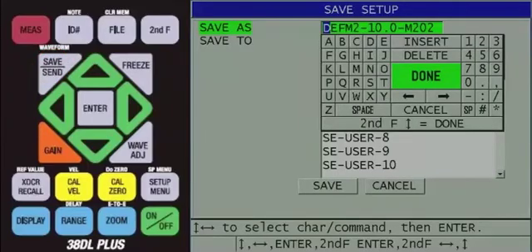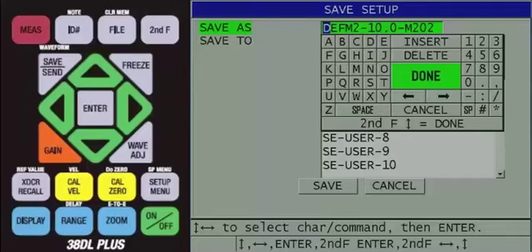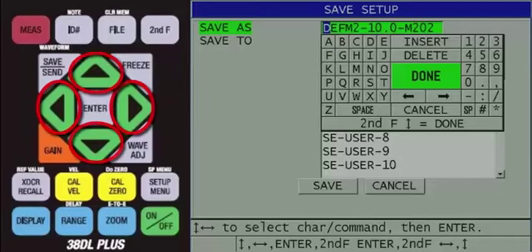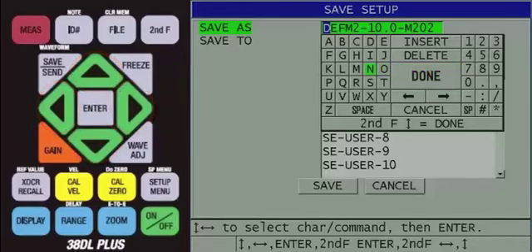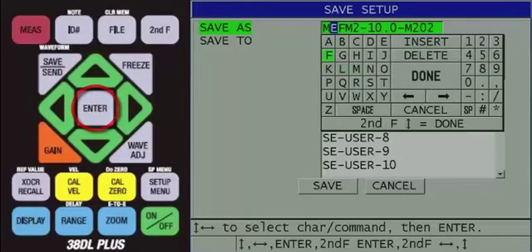Here, you will notice that save as is highlighted and a virtual keypad appears on screen. You can now use the keypad on screen to enter a name for the custom transducer setup. Use the arrow keys to highlight a character, then press the enter key to input the character into the save as line.